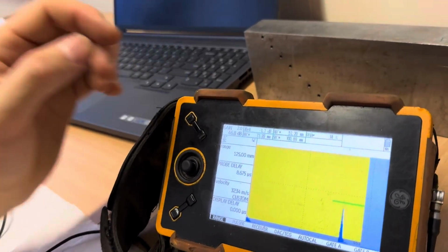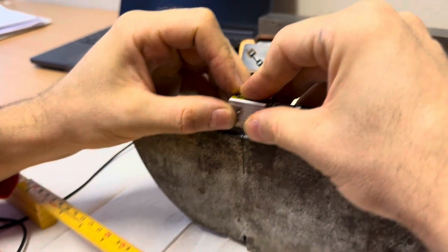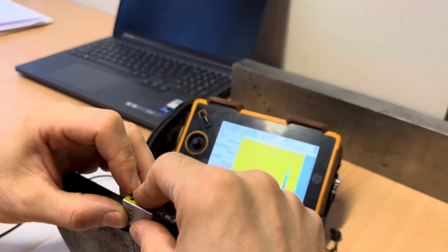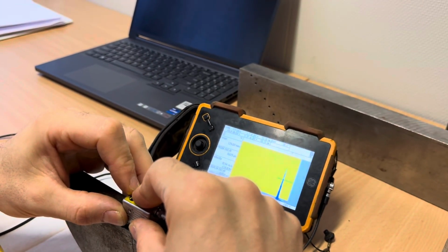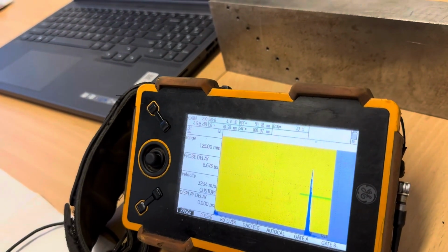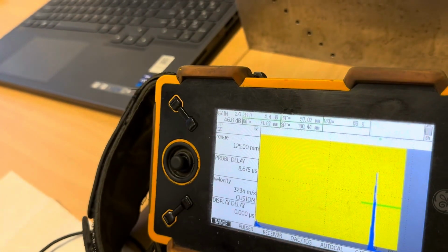We consistently find the strongest and most prominent signal. Before this, we had already meticulously set it up so that it should clearly show a significant amplitude at a precise depth of exactly 100 millimeters. We adjust for the strongest signal and we see that it shows exactly 100, about 100.